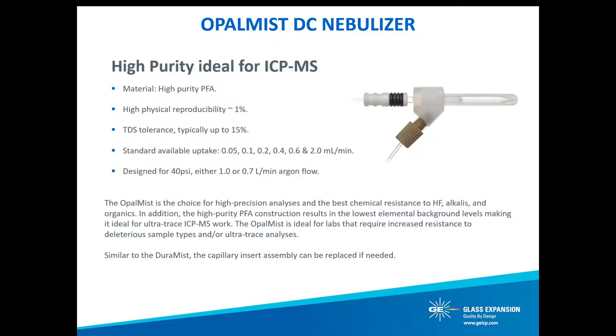The Opal Mist is our concentric nebulizer made from ultra-high purity PFA and is the choice for high-precision analyses with the best chemical resistance to hydrofluoric acid, alkalis, and organics. The high-purity PFA construction results in the lowest elemental background, making it ideal for ultra-trace ICP-MS work. Similar to the DuraMist, the capillary insert assembly of the Opal Mist can also be replaced. The Opal Mist is an ideal choice for labs that require increased resistance to caustic sample types and/or ultra-trace analysis.